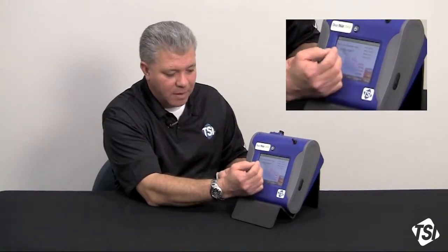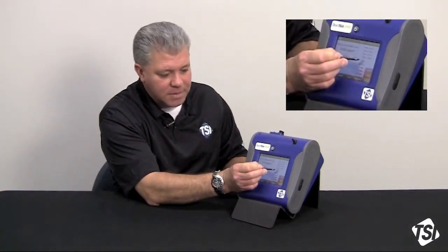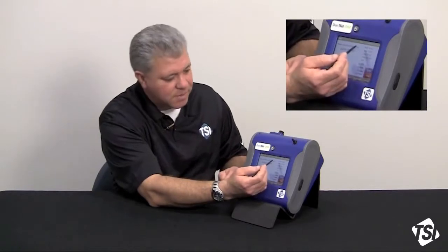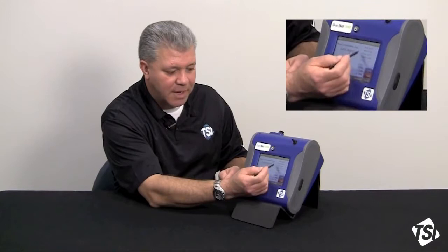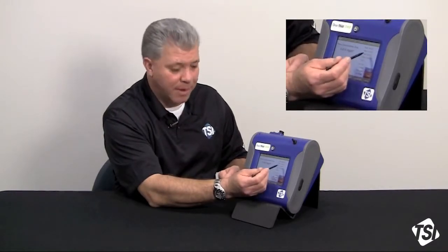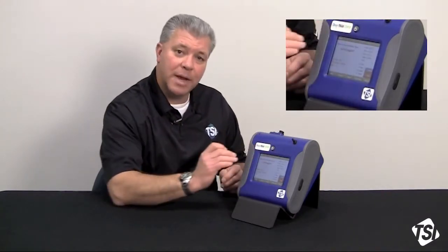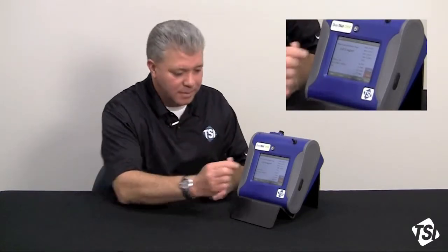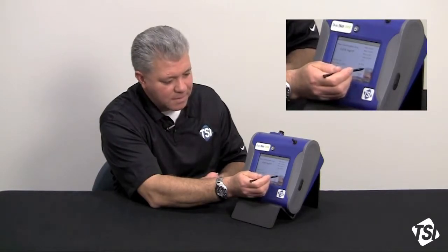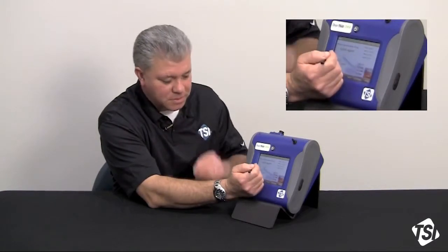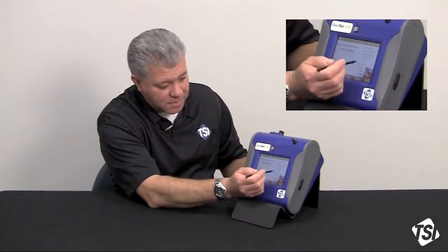Now, if I want to look for the stats associated with this sample, I push the stats button, and over on the right hand side of the screen, my stats change. I have min, max, average, and time-weighted average data to look at during sampling. Very important to be able to look at data while you're taking a sample. Okay? If I touch the stats key again, I go back to having my regular concentrations displayed for all 5 size fractions.